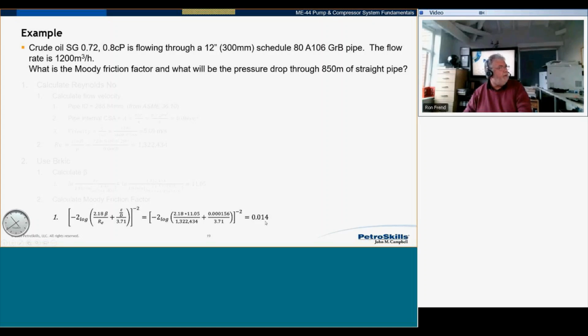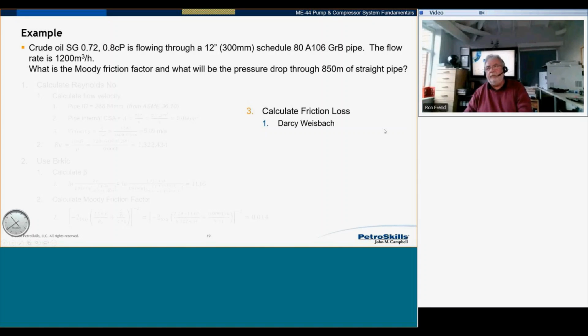Now I know what the Moody friction factor is. I can now calculate my friction loss. I'm going to use Darcy. And L over D, 850 over 0.289. V squared, we said was 5.09. Comes out at 54 meters. Convert that into pressure using rho g h, and that comes out at 385 kilopascals.